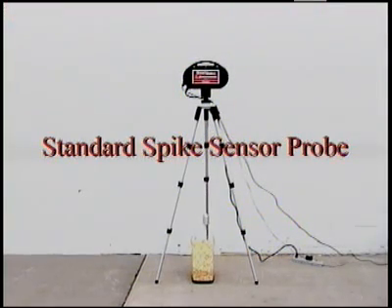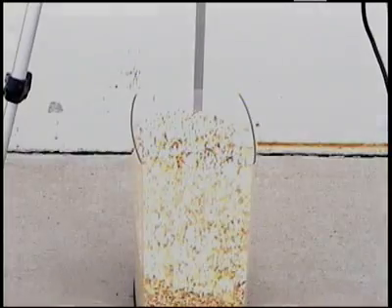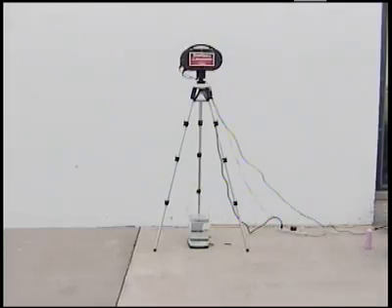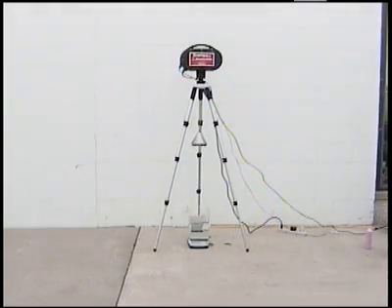SmartBOB2 comes standard with a cast stainless steel spiked sensor probe. This is designed for powder and granulars with angle of repose. A hollowed six inch stainless steel inverted cone is designed for liquids. Teflon coated cone is available for sticky and corrosive materials.